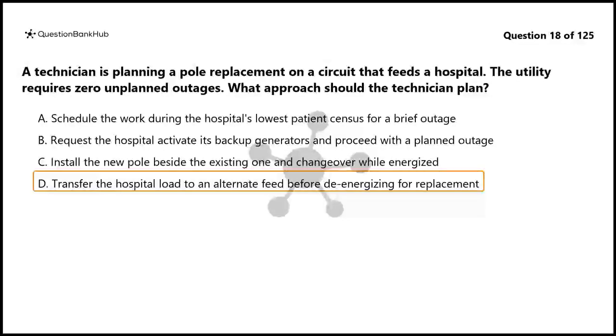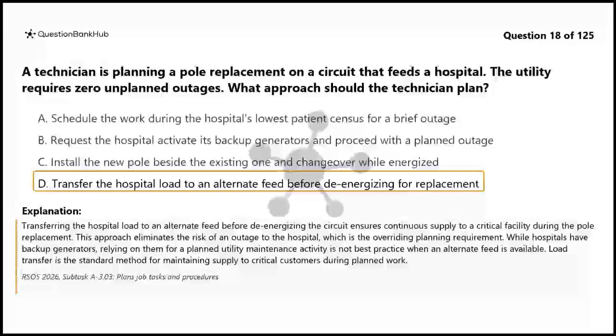The correct answer is D. Transferring the hospital load to an alternate feed before de-energizing the circuit ensures continuous supply to a critical facility during the pole replacement. This approach eliminates the risk of an outage to the hospital, which is the overriding planning requirement. While hospitals have backup generators, relying on them for a planned utility maintenance activity is not best practice when an alternate feed is available. Load transfer is the standard method for maintaining supply to critical customers during planned work.